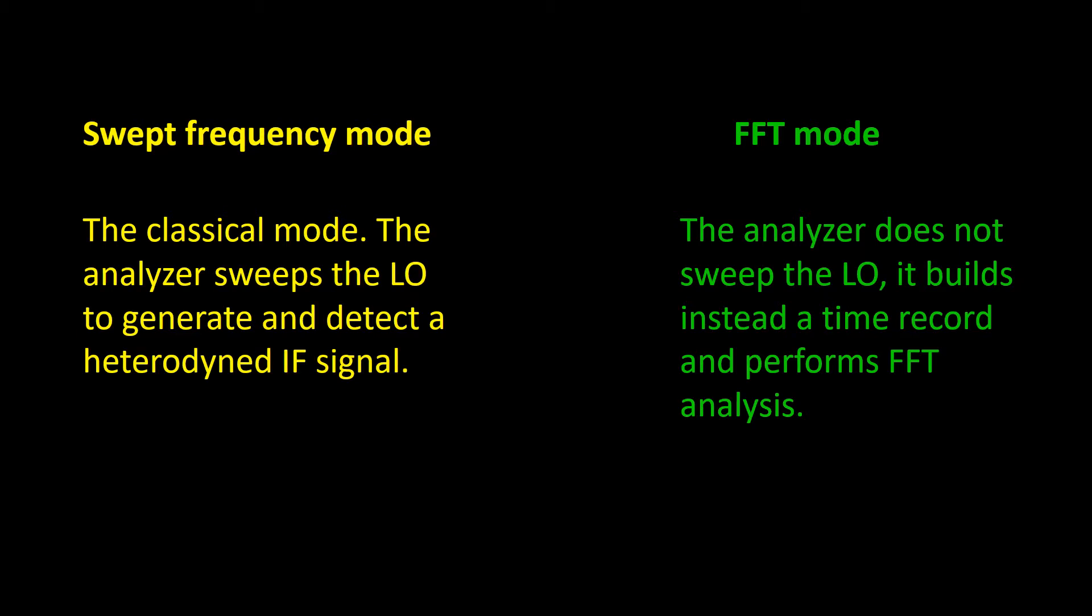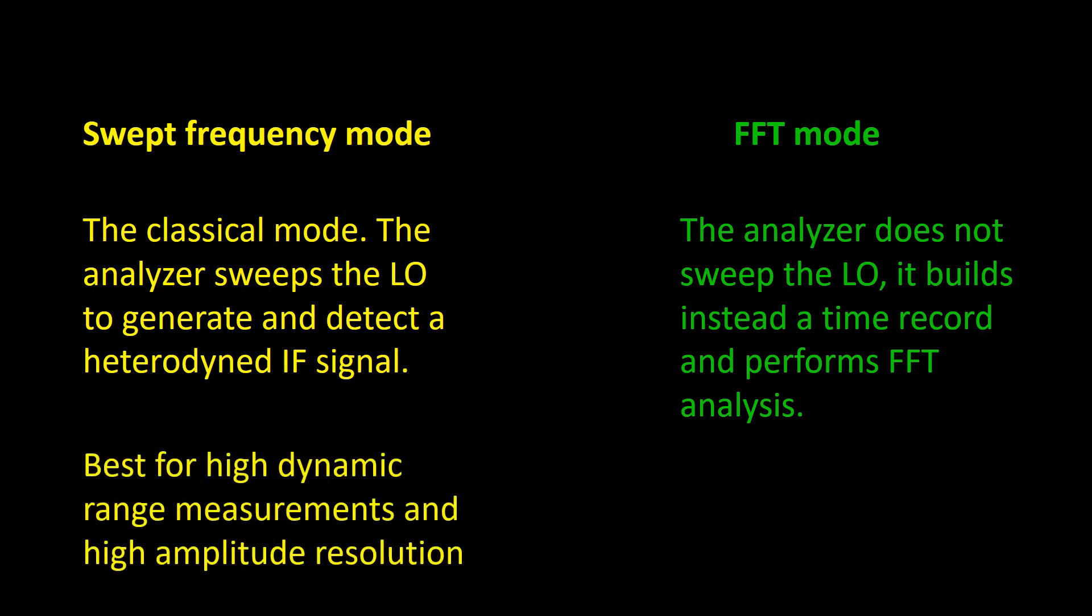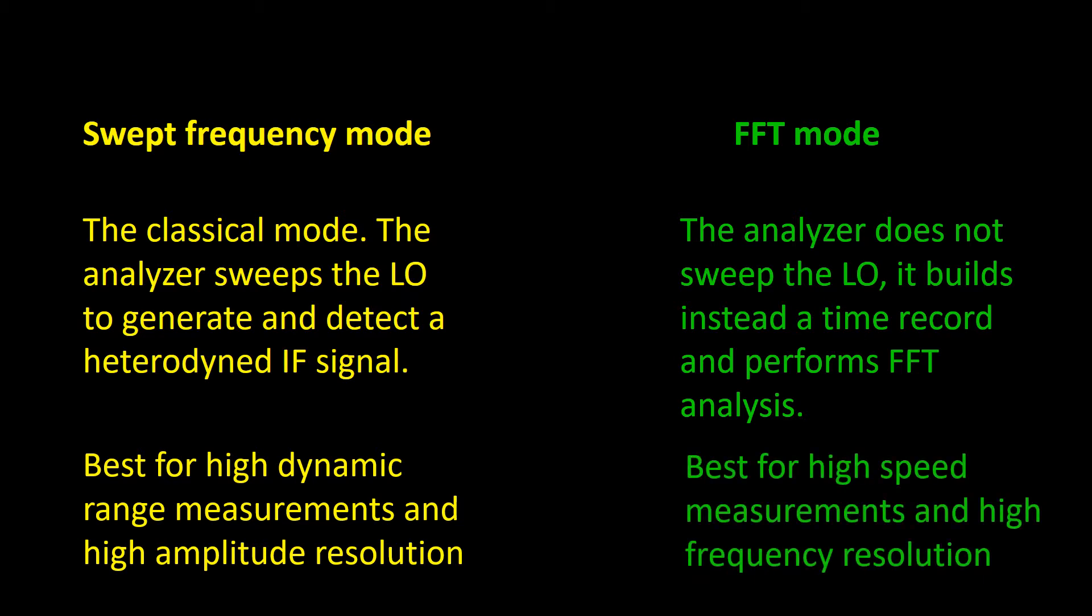Depending on your needs, you may prefer one mode or another. If dynamic range and amplitude resolution are important to your measurement, you will probably use the swept mode. But if you need faster sweep speeds at narrow bandwidths, the FFT mode will be your best option.